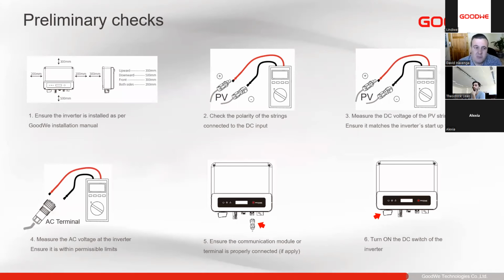It's always good to do preliminary checks, although our inverters do have reverse polarity protection. It's always best not to put it to the test and check these strings correctly to make sure our strings are correct, as well as the AC wiring. And always remember, most of our devices have a DC switch underneath that needs to be turned on for it to see the DC.